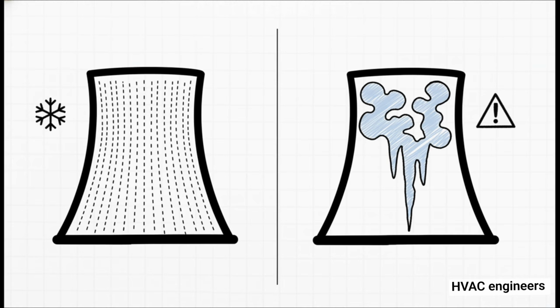Counterflow systems, though, get into real trouble if you push them below 70% capacity. The water loses pressure and you get what's called channeling, where the water basically clumps together, leading to unpredictable cooling performance and, dangerously, hidden ice buildup inside the tower during winter.